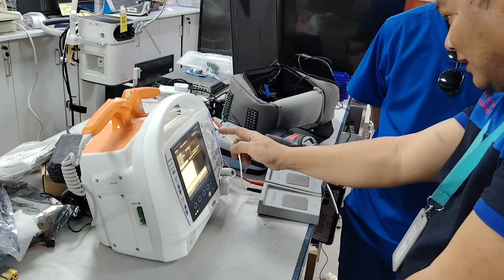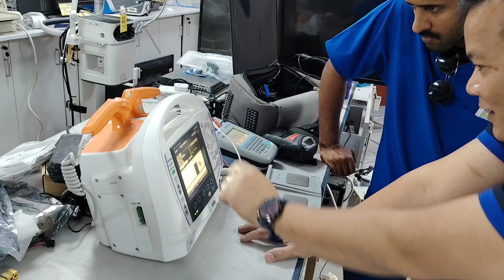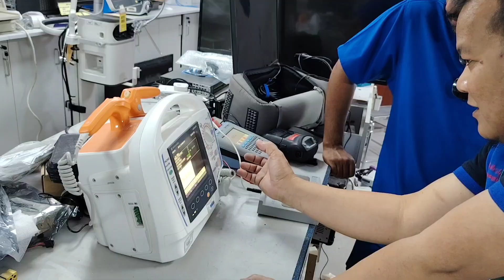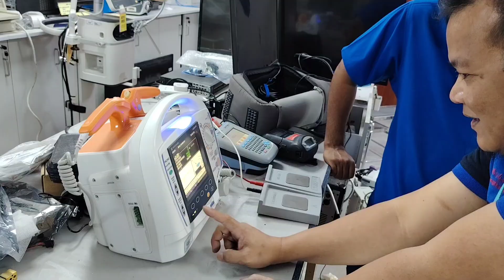See? Stop key. This start stop key, they will check okay or not okay. Pacing check, this is the pacing key, this is pacing check. They will check the pacing of the defibrillator. See, the pulse is here, it's blinking. Now it's okay. Next, check this one, red. It's okay, red. Yes. Check this one, green. Green. Yes. Testing voice instructions. Voice instructions okay. Yes. Red. Yes. Yellow. Yes. Blue. Yes.